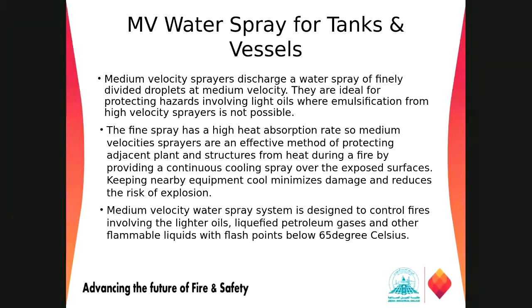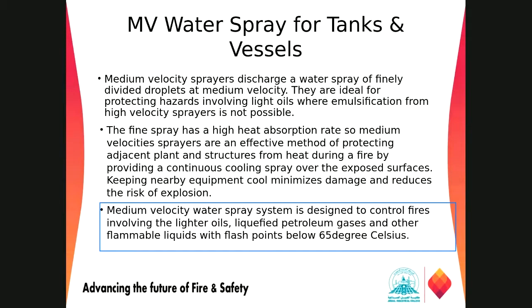This is one of the effective methods for protecting nearby plant and structures from heat during a fire, by providing a continuous cooling spray over the exposed surface for some time. It is intended to protect liquids such as lighter oils, liquefied petroleum gas, LPG, and other flammable liquids with a flash point below 65 degrees Celsius.